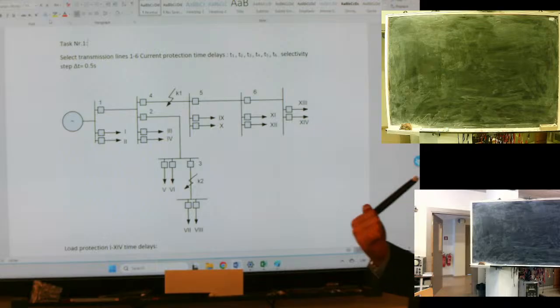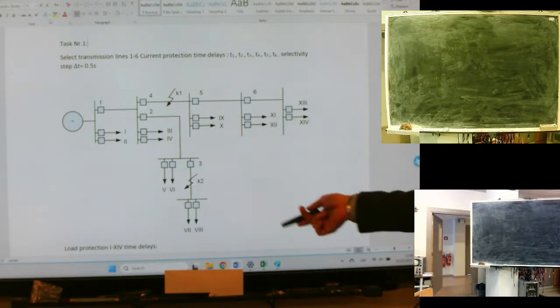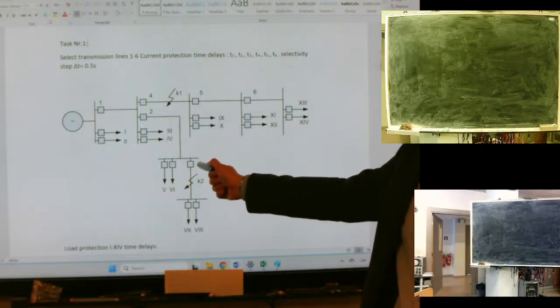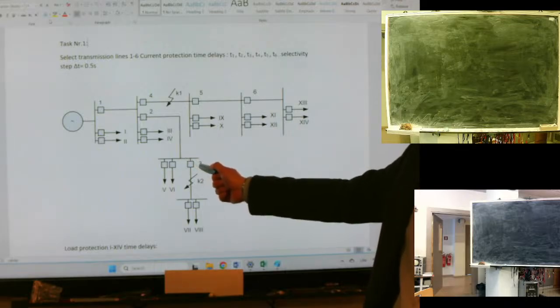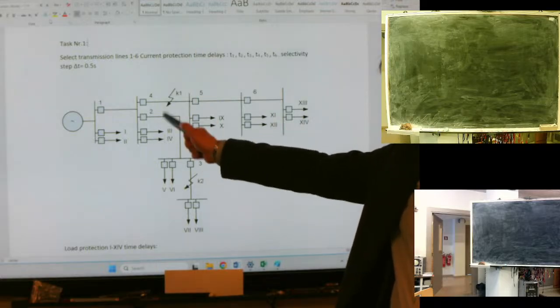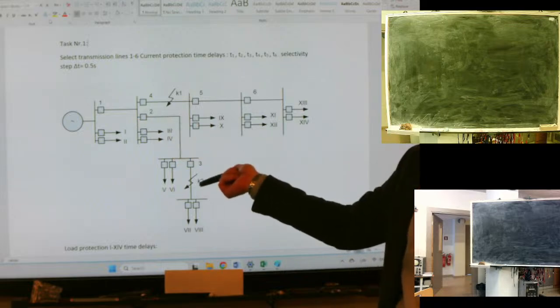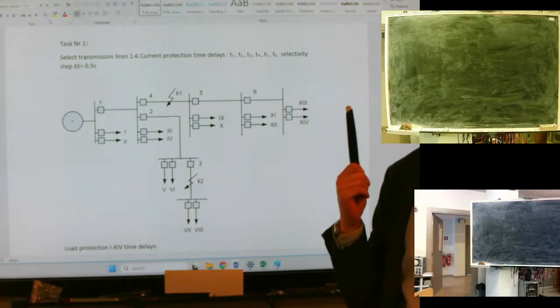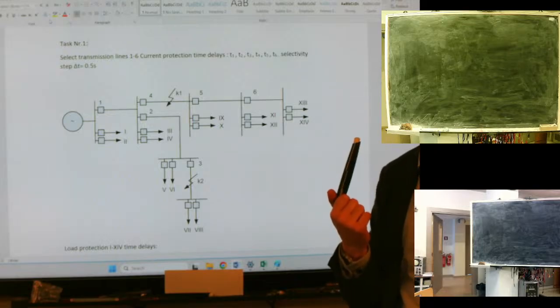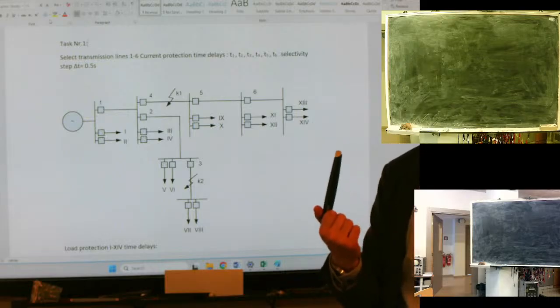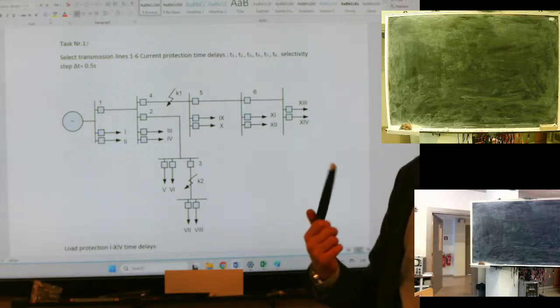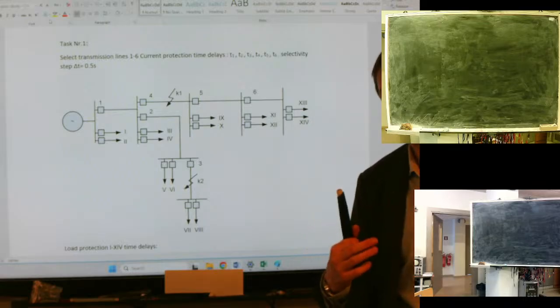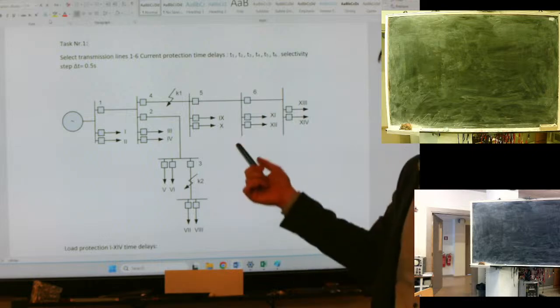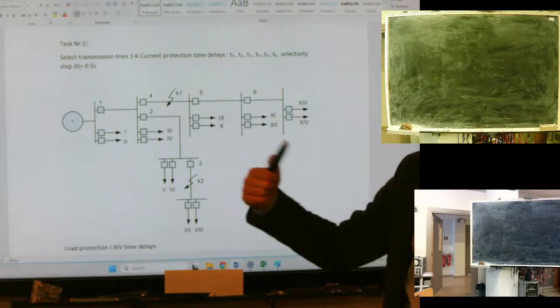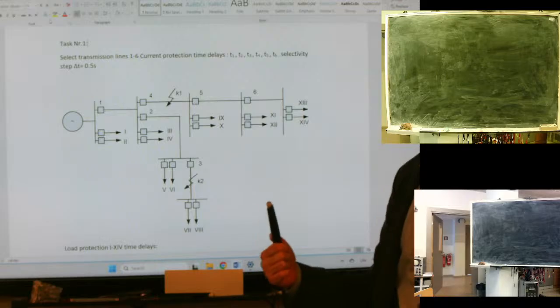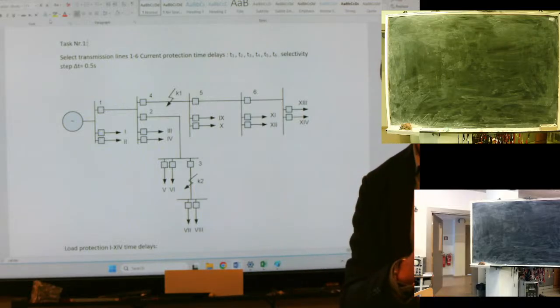And in this case, we have one more question based on this topology. Okay, the first to disconnect is number 3. But do we want other protection in series, number 2, number 1, to detect this fault? There are two logics. The first one is to detect the fault, because if the protection device can't detect the fault, it can't send the signal to disconnect the circuit breaker. And in this case, we separate two definitions: to detect and to send the signal to disconnect. Because if we send the signal to disconnect, it means that we are disconnecting. But there is a time delay from the moment when we detect to the moment we send the signal.